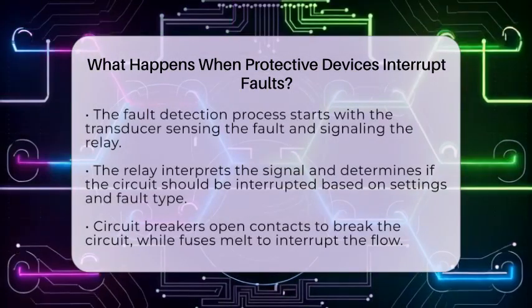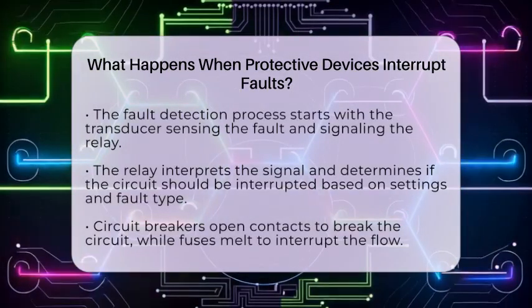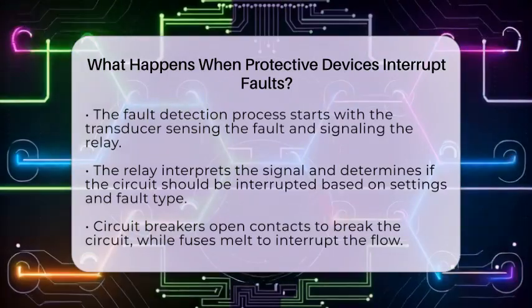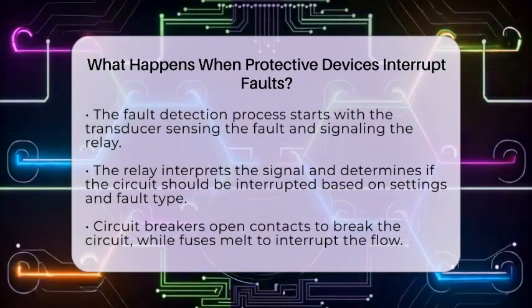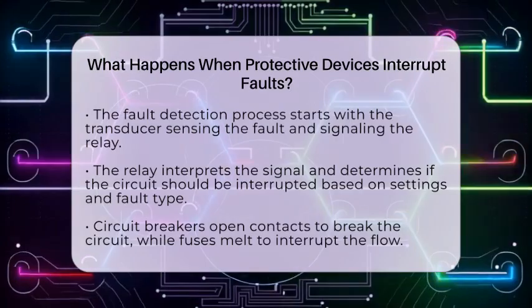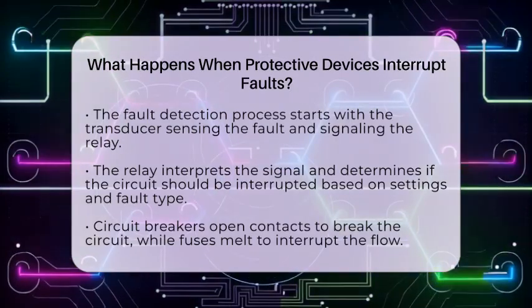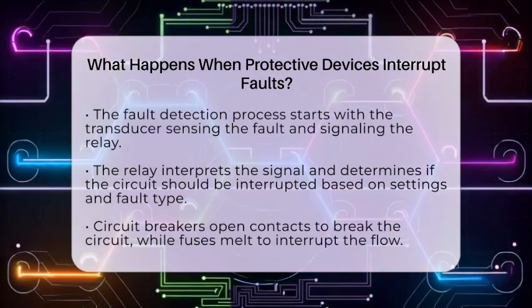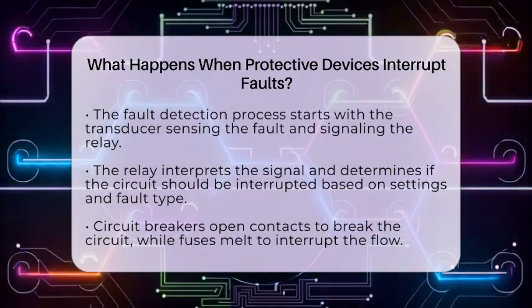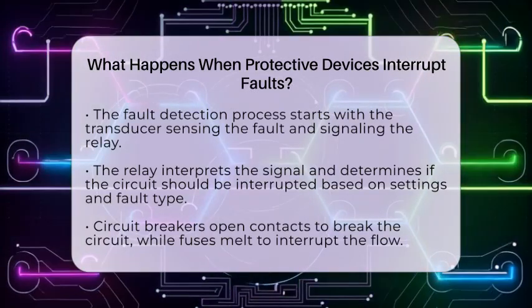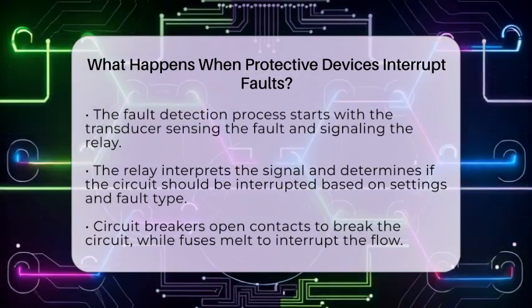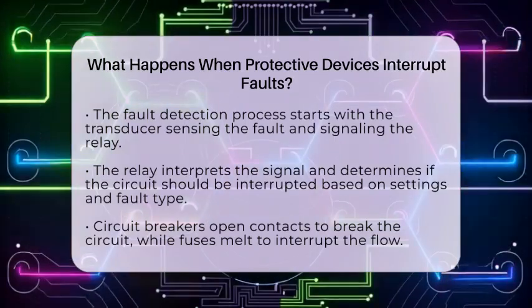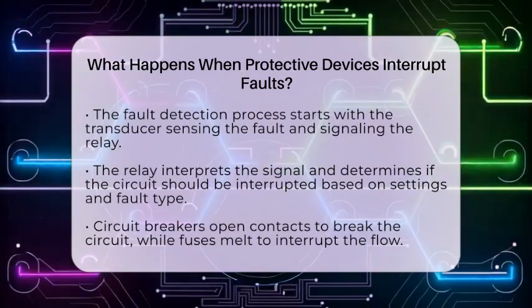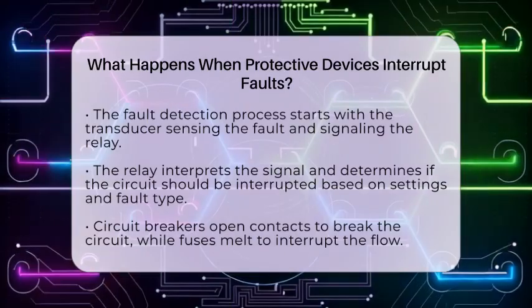Next, the relay interprets this signal and decides whether to initiate the interruption process based on predetermined settings and the type of fault detected. Once the relay decides to interrupt the circuit, it sends a command to the circuit interrupter. For circuit breakers, this involves opening the contacts to break the circuit. In the case of fuses, the excessive current causes the fuse element to melt, thereby breaking the circuit.